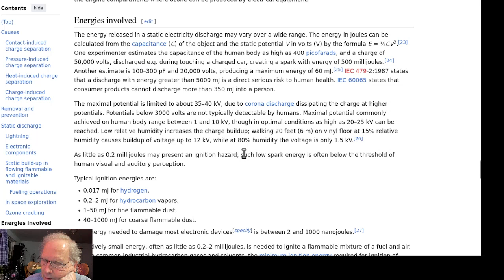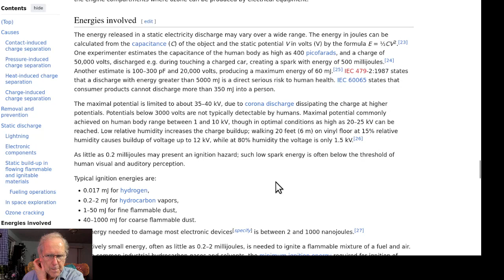Here, it says right here: relatively low relative humidity increases the charge buildup. Walking 20 feet on a vinyl floor at 15% relative humidity causes a buildup voltage of 12,000 volts, while at 80% humidity, the voltage is only 1.5 kilovolts. So yeah, at 80% humidity, you're not gonna get zapped on anything. You're not gonna get static. You're not gonna see any static electricity.